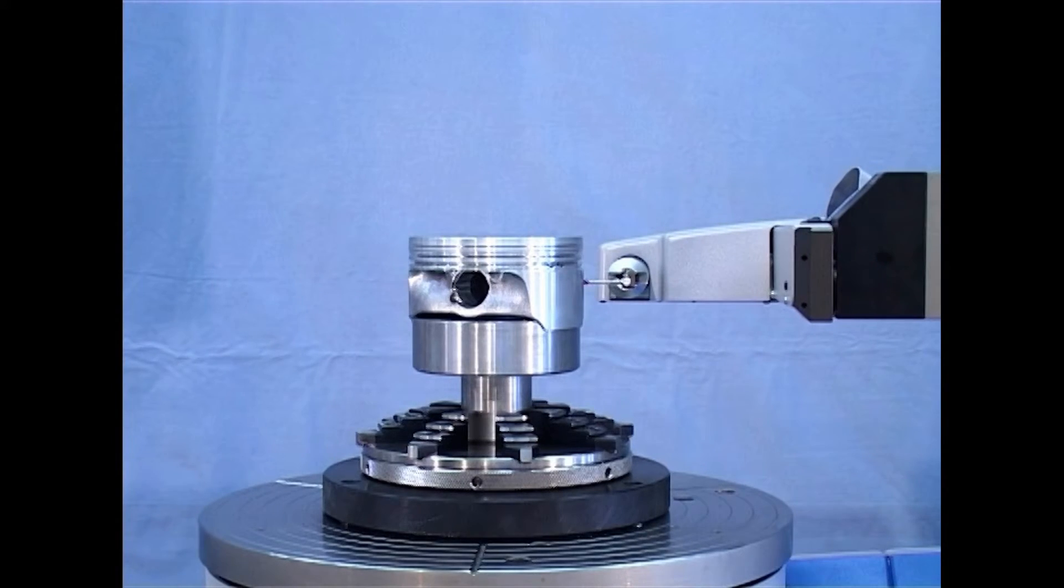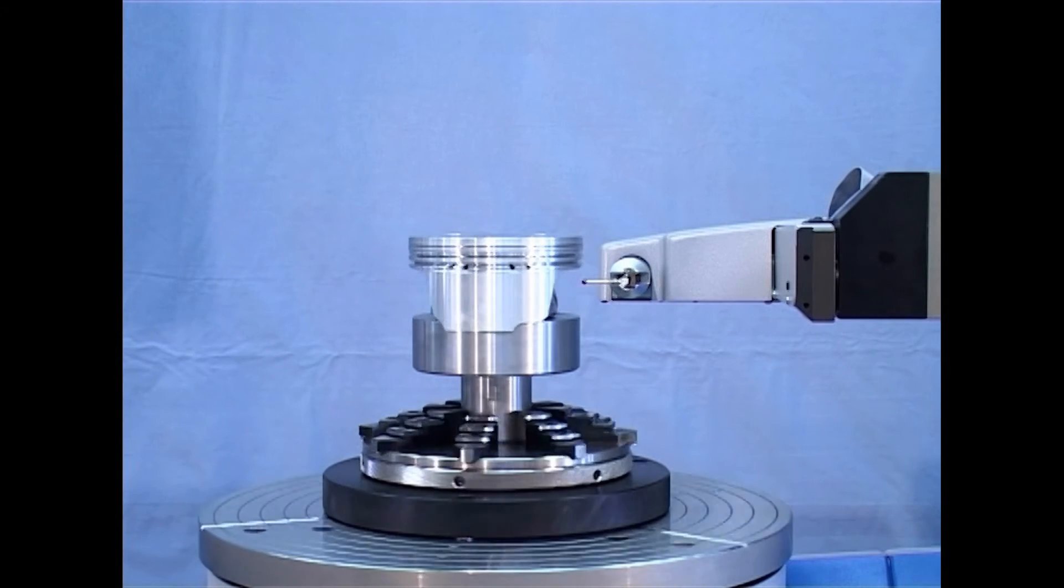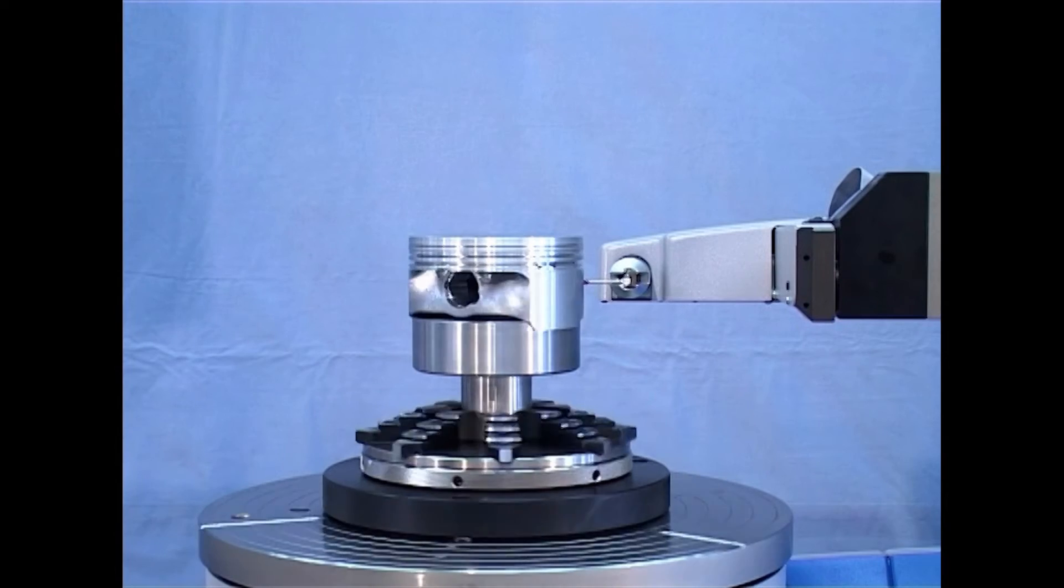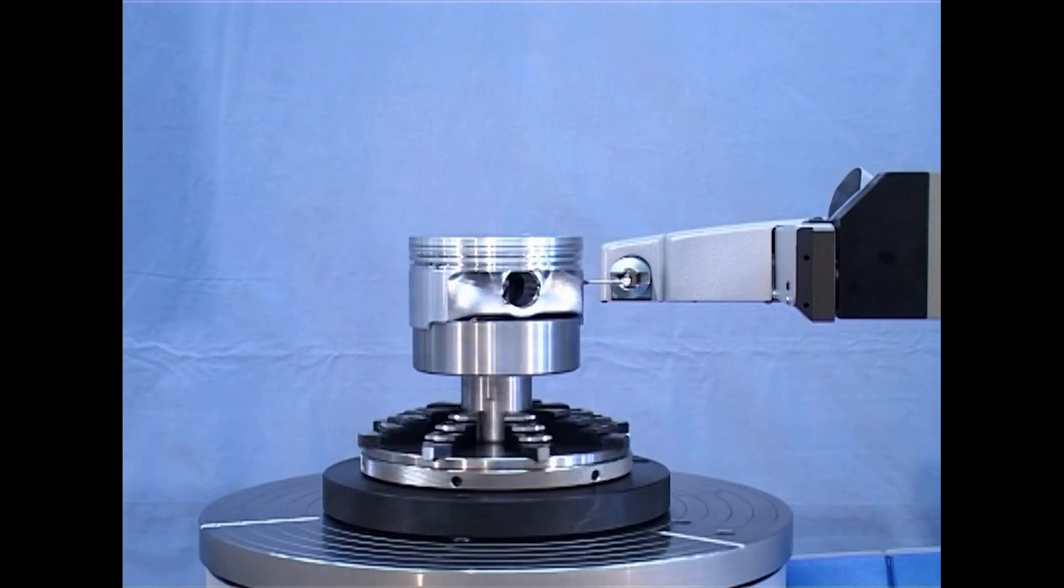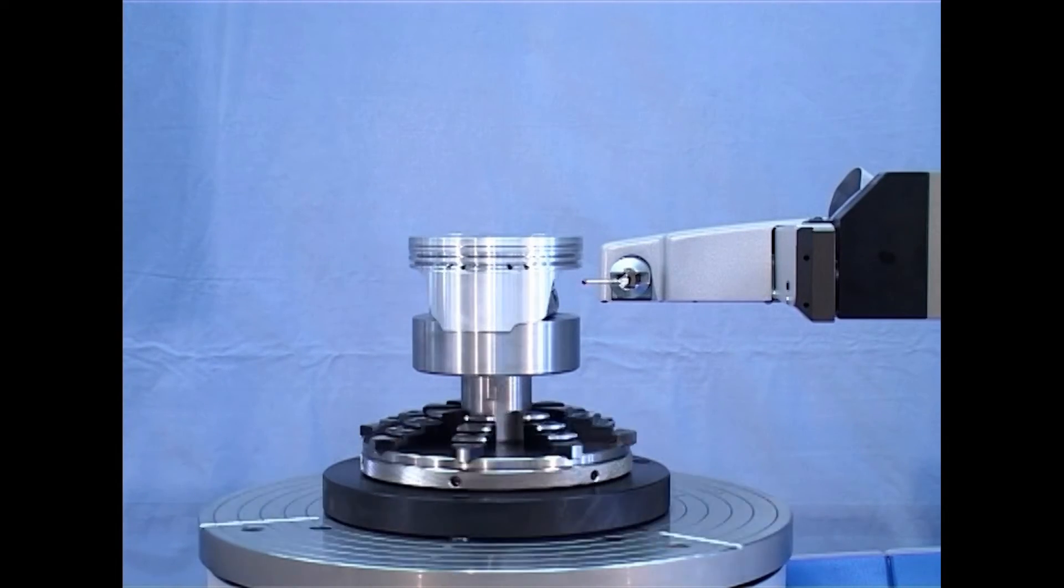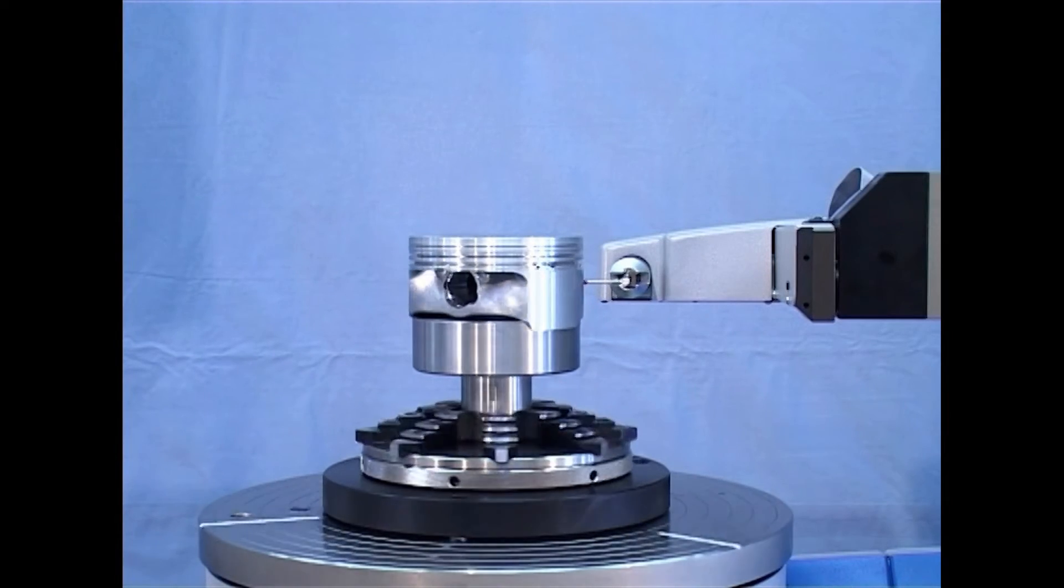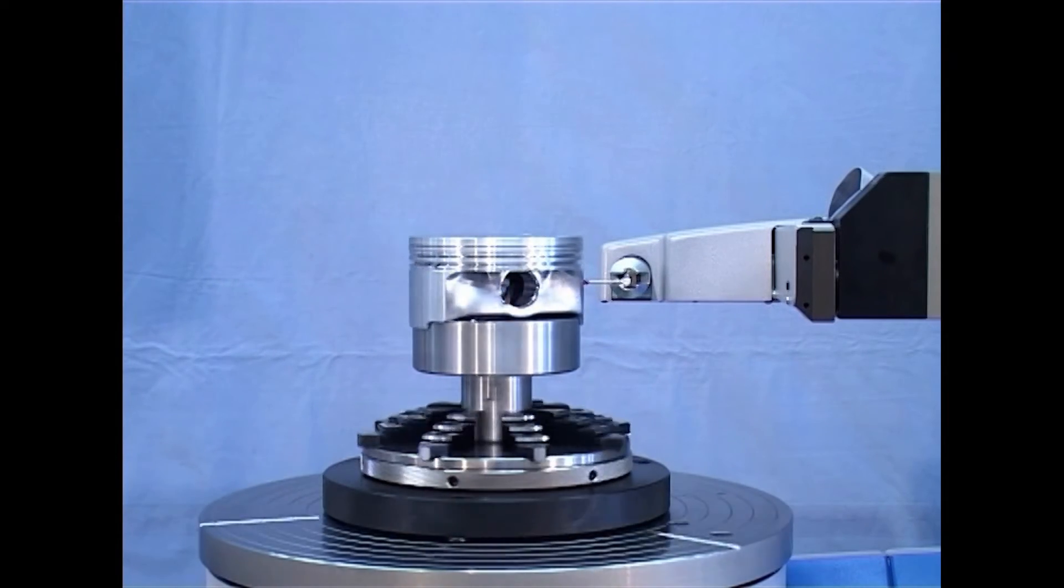An additional advantage is the large measuring stroke of the scanning system of plus minus 1500 micrometers, which has an excellent linearity over the whole measuring range. This also enables measurements on workpiece geometries with considerable unroundness.